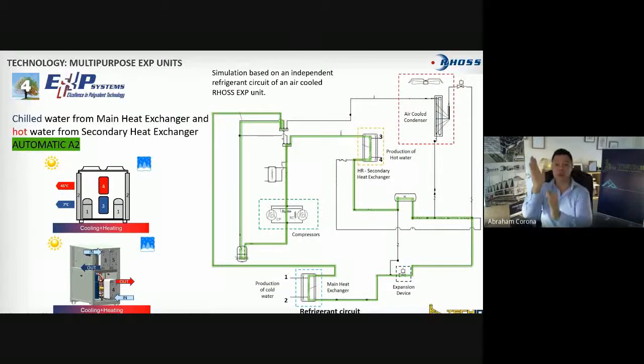The main difference now is that, before, we swapped the refrigerant from the air-cooled condenser into an extra heat exchanger, that is the main heat recovery, total heat recovery, and we start to produce water at maybe 45 to 55 as the set point. So we are recovering that heat that we before were wasting into the environment. We recover that heat, we use the heat recovery as a condenser, we condense the refrigerant there, we come back to the expansion device, and we complete the cycle.